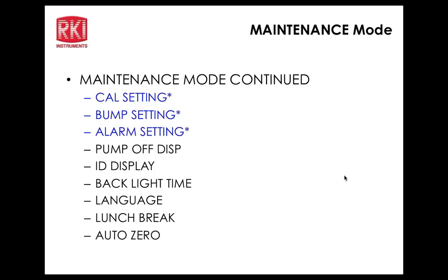Confirmation beep, key tone. So we've been listening to this key tone all along here. I can turn it off right here if I want to. So that's that function. Inert mode. So you can turn the unit into inert mode or not. Now you notice that this is in the maintenance mode here, not the factory mode, whereas on the Eagle 2, that function is in the factory mode. Okay, so a little bit of a difference there between the two units.